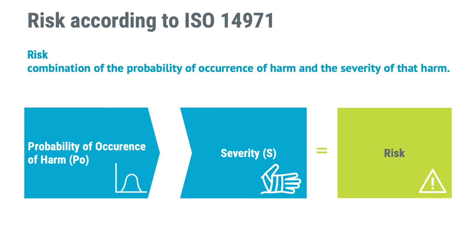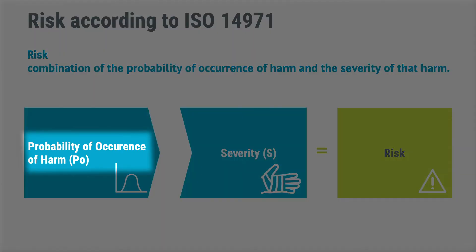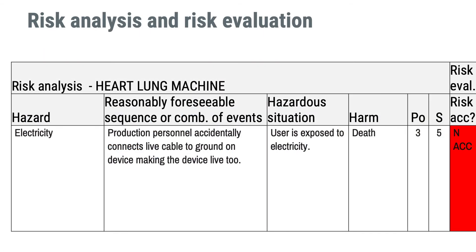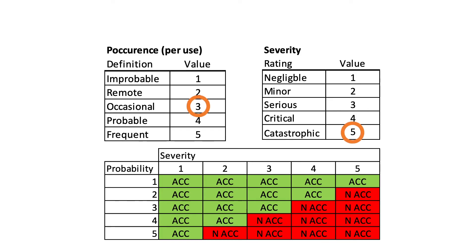In ISO 14971, risk is defined as the combination of probability of occurrence of harm and the severity of that harm — often abbreviated as PO and S. When estimating the probability of occurrence of harm, you should think of your product as if you haven't implemented any risk control measures at all, meaning that the probability is fairly high — on a scale from one to five we set it to three. The severity is based on the harm, which in this case was death, so we assign the highest severity: five on a one-to-five scale.